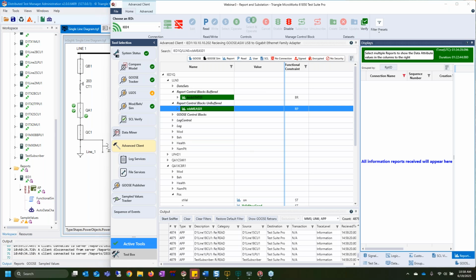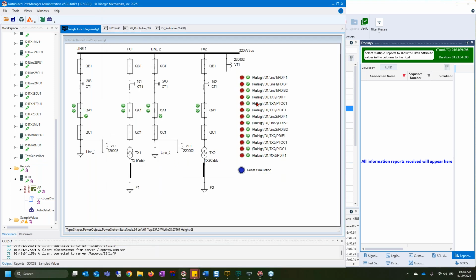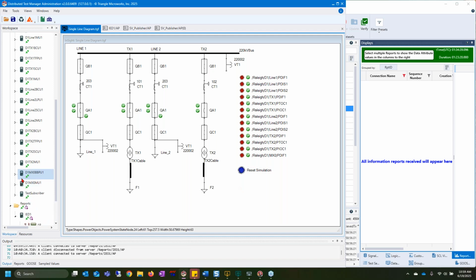All right, so as Jackson mentioned, a lot of the capabilities of your devices when it comes to GOOSE are all within the SCL file. Well, we use those SCL files to build up the Test Suite Pro or TSP workspace. In order to monitor and do the automated protection within the electrical equipment outlined in the single line diagram, there's a lot of GOOSE messages going back and forth, and a lot of devices rely on what typically in other protocols might be communicated across that copper wire.